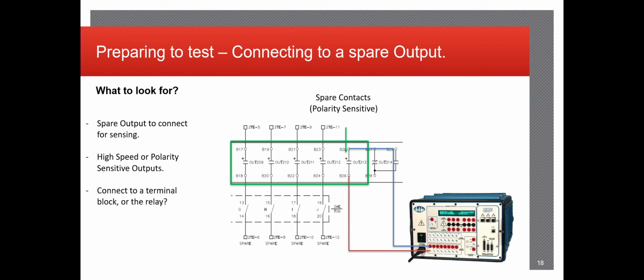A lot of times I've run into this. You're running the test and you know the relay element's picking up because you're looking at the SER, and you just forgot to set the output to whatever element you're supposed to. So the test is working, but your test set doesn't see it and thinks it's a failed test every time. So there are a lot of little things that you'll encounter if you're a relay tester that can make you scratch your head, and you end up looking back and being like, oh, that was just so stupid.